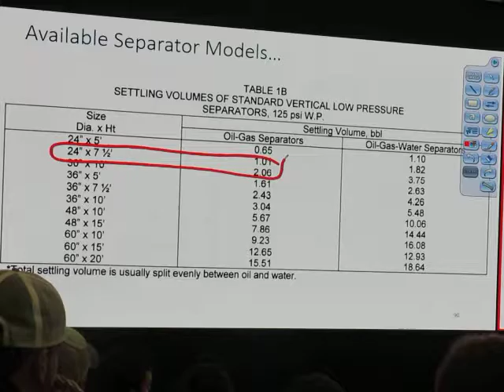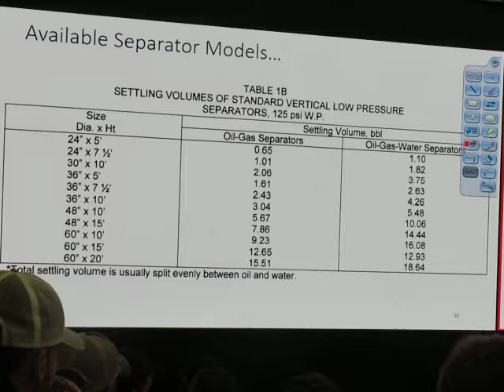So this chart gives me settling volume for the vertical separator. Alright. Now there's a problem with this. This is if we operate it the way that they recommend. They recommend half full, we operate half full. If we decide to operate less than half full, maybe we have less settling volume. You see what I'm saying? So the liquid height in the separator actually matters. If we don't do what the manufacturer recommends, we use a full calculation.